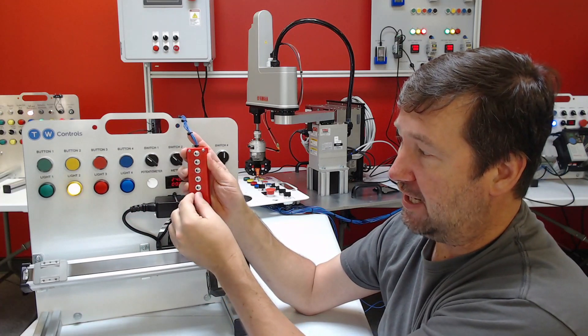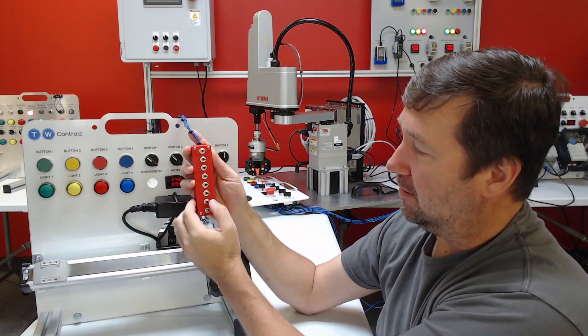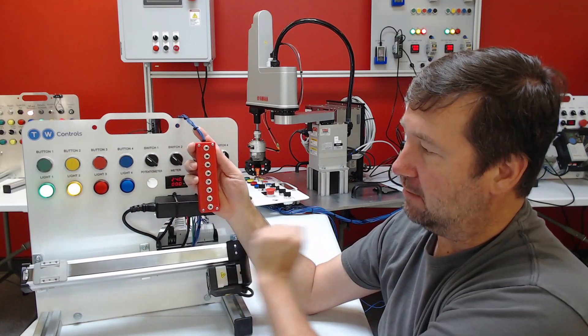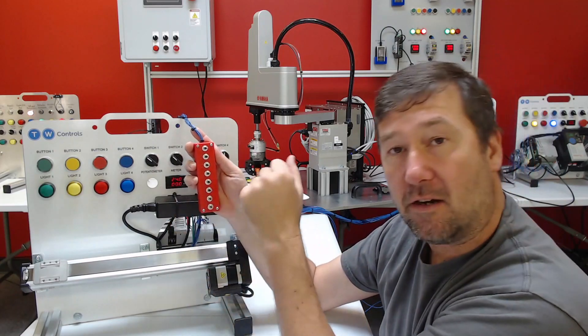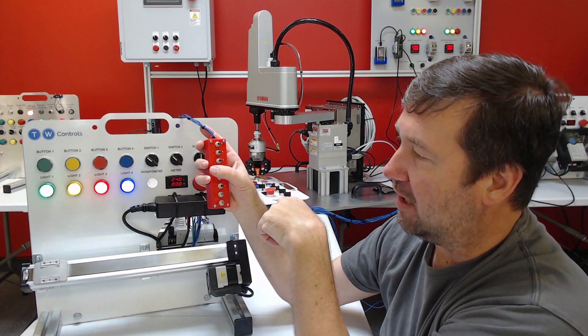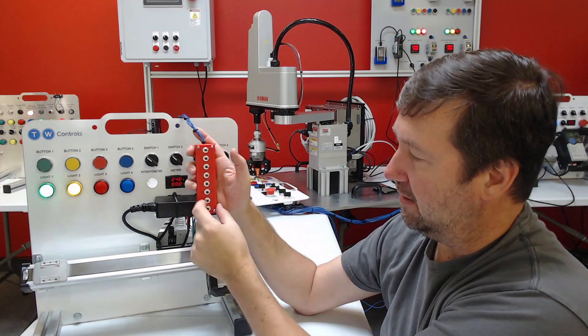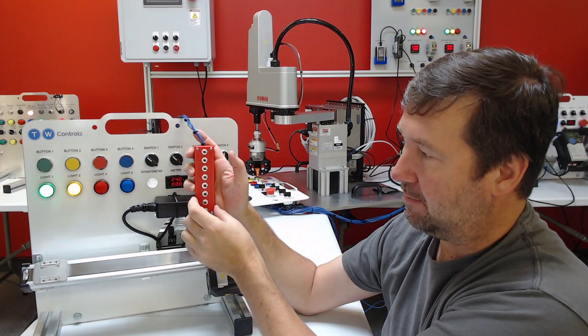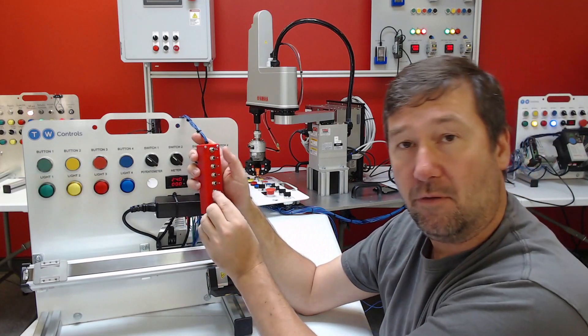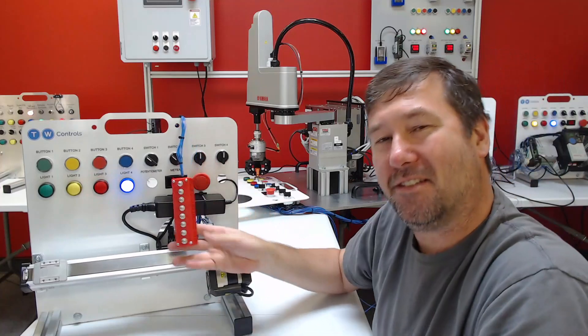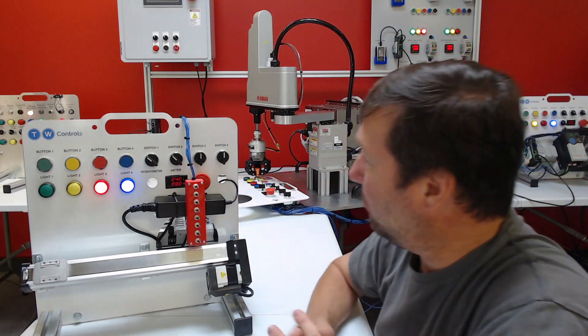Also if it keeps going up the second will come on. And let's just say for some reason that our lead and our lag are not working. The high float should still operate our system. And let it pump back down to either the stop or the low alarm float. So I think this will make a good challenge. I look forward to seeing what all you come up with.